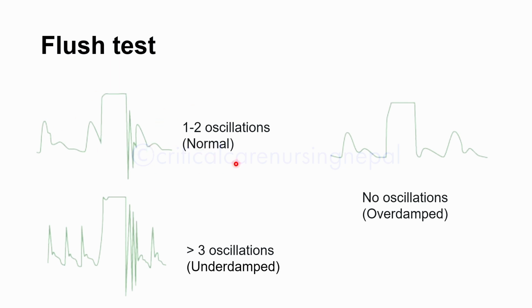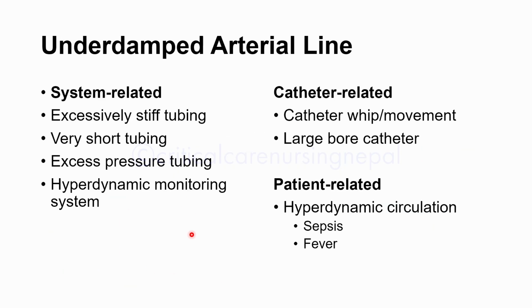So this is the normal waveform, the normal flush test result. But if you see a lot of ringing or more than 3 oscillations, then it means underdamped. More than 3 oscillations means underdamped. And if there are no oscillations, it means overdamped. Remember, no oscillations, overdamped. More than 3 oscillations, underdamped. This is how you can trust your values using the flush test. If it is 1 to 2, trust your monitor readings. But if it is more than 3 or no oscillations, both are dangerous, and you need to recognize them in time. So let's see what the causes of an underdamped arterial system are.